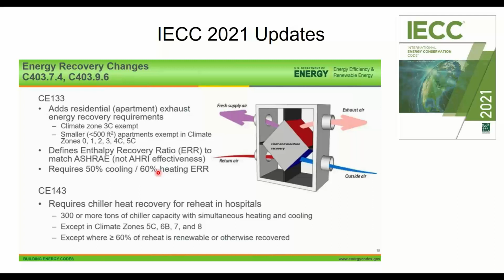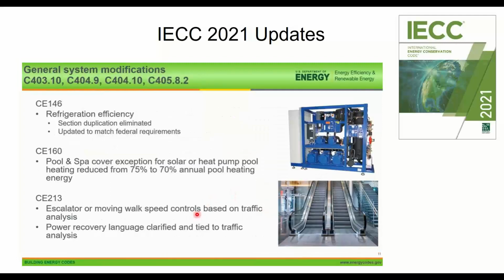If you're doing chiller heat reclaim stuff, which we do a decent amount of here at TEC, there are some additional requirements kicking in, specifically related to hospitals. Right now we do it a lot on places with swimming pools and similar situations where you have simultaneous heating and cooling needed. But they're recognizing that in hospitals, there's pretty much reheat needed most of the year if not all of it, so they're requiring it more strictly in hospitals now than before.